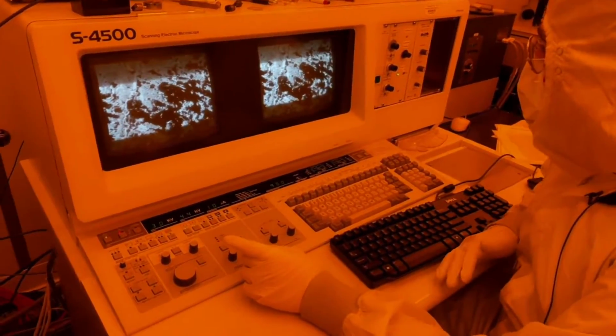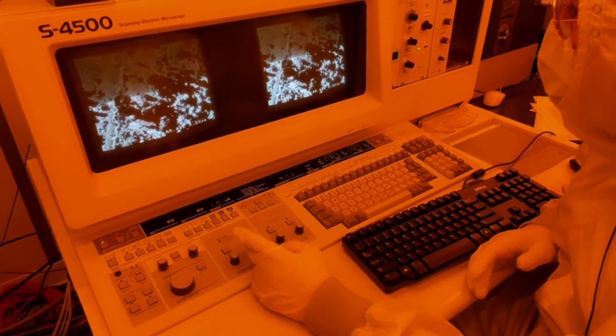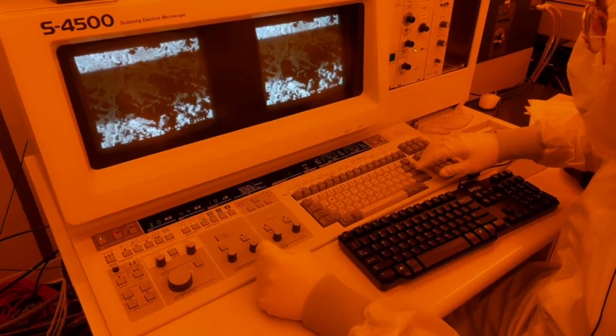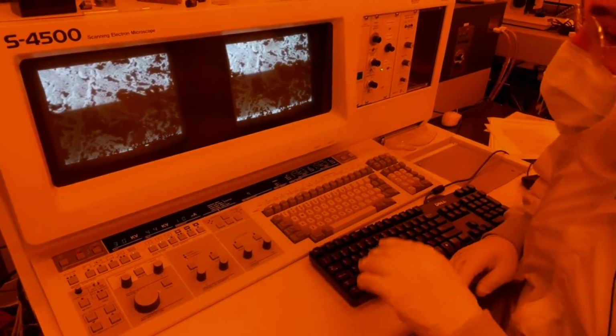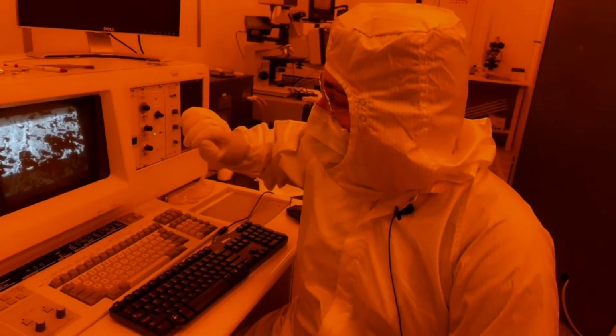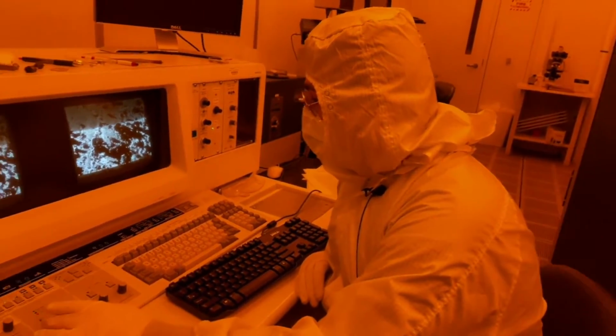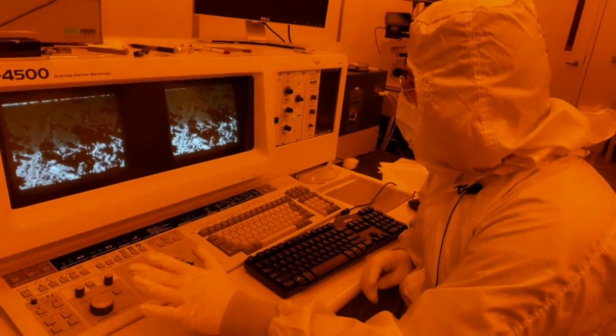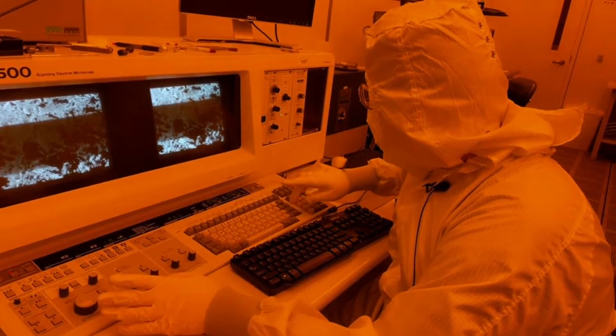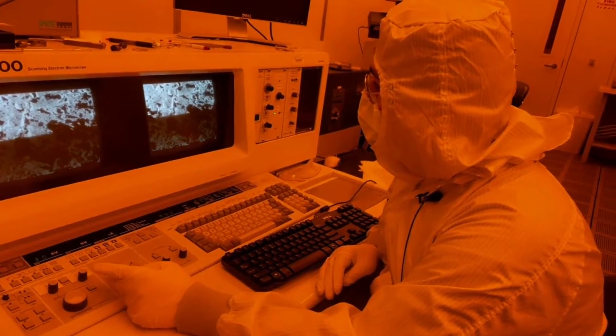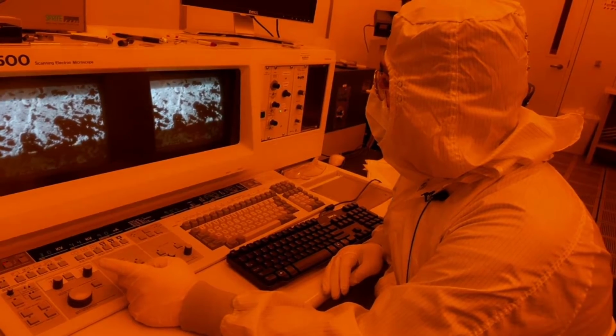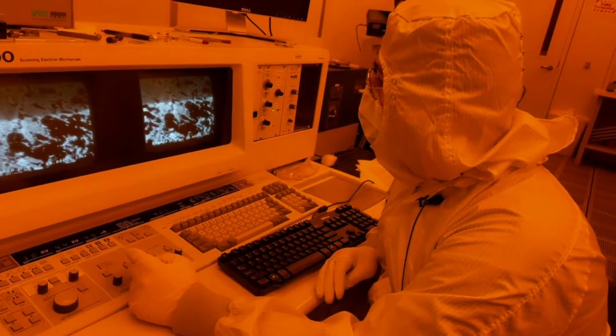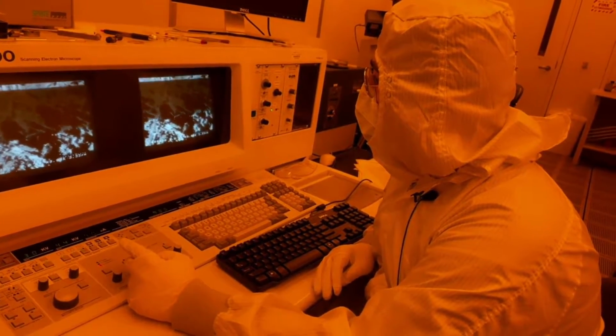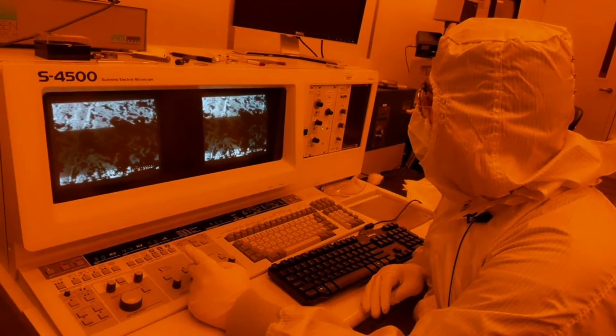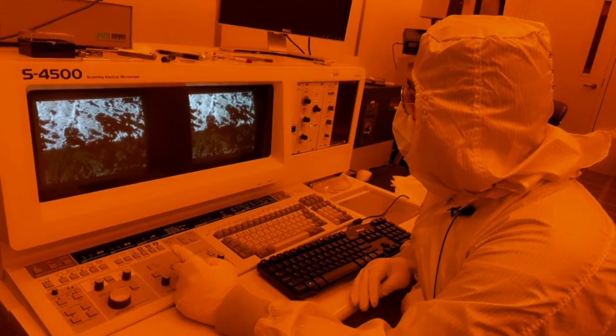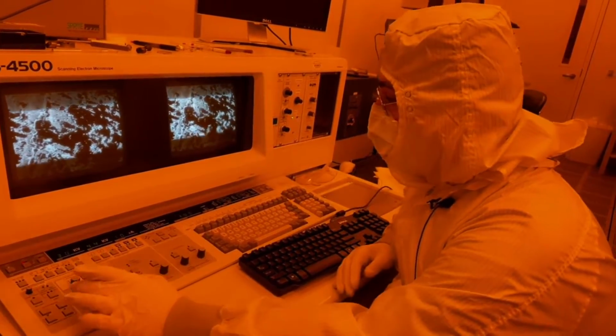Next, we're going to do a stigmation alignment. This does the same thing, but with the stigmators. As you can see, it's barely moving. Usually these stigmators don't get very unaligned. But with this one, as opposed to the aperture alignment, you can actually get it to stop completely, whereas with the aperture alignment, it's going to keep wobbling to some extent. So that's in the X direction. Now we're going to align the stigmators in the Y direction. There we go. And then now we can press exit.